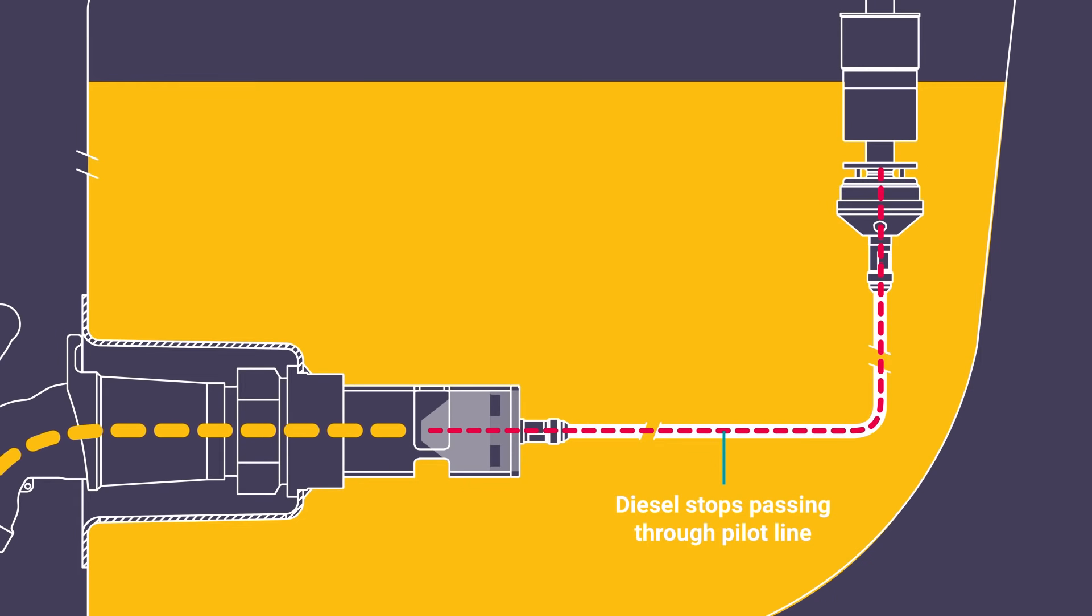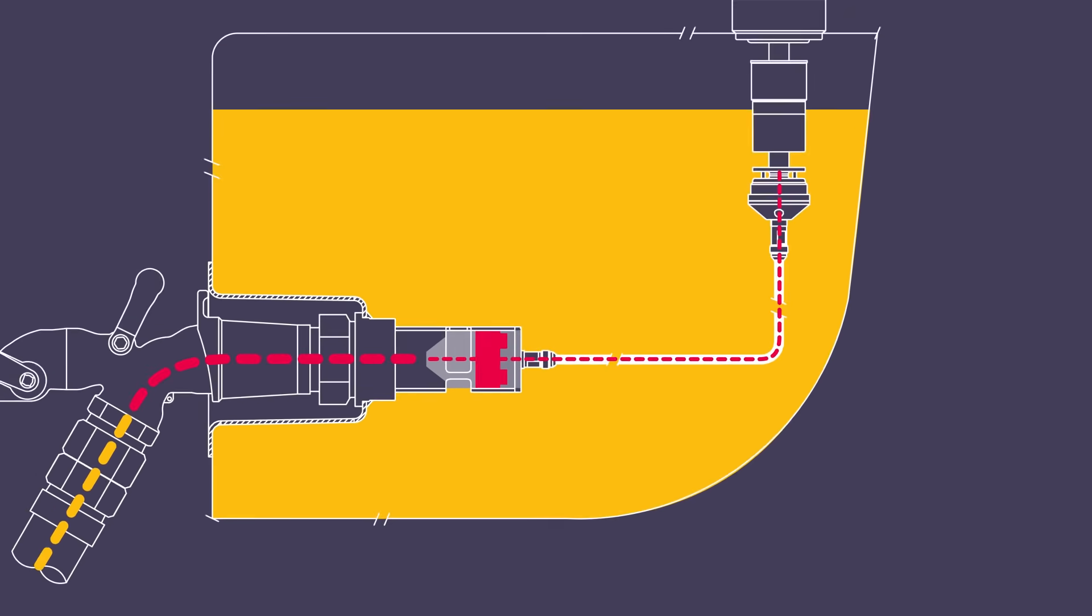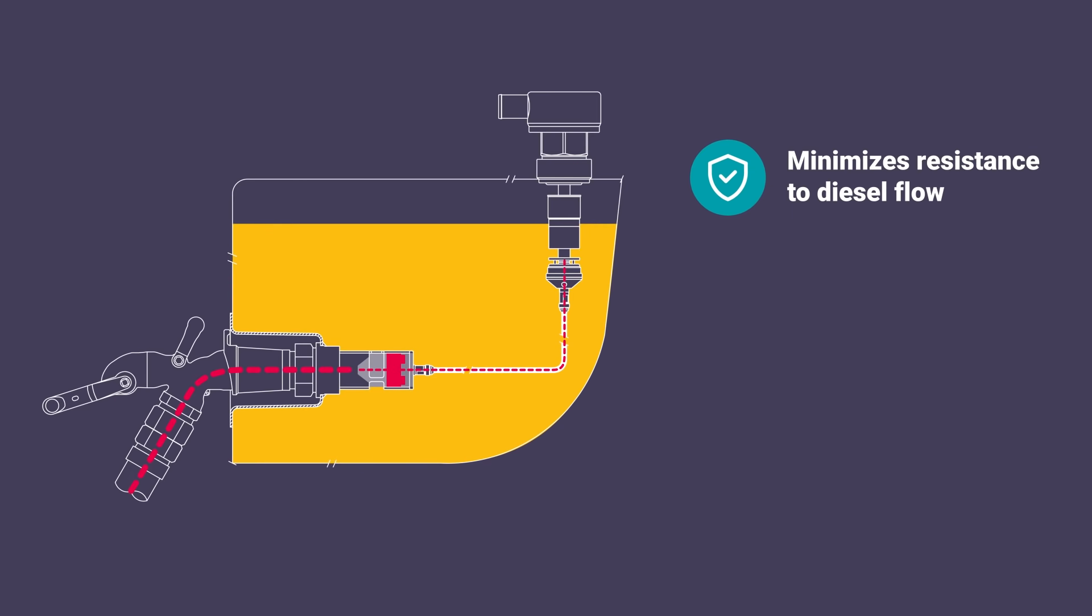As soon as diesel stops moving through the pilot line, the flow control valve is triggered to close. This clever design minimizes the resistance to fuel flow, ensures zero pressure buildup in the tank, and rapidly terminates filling when the correct ullage is reached.